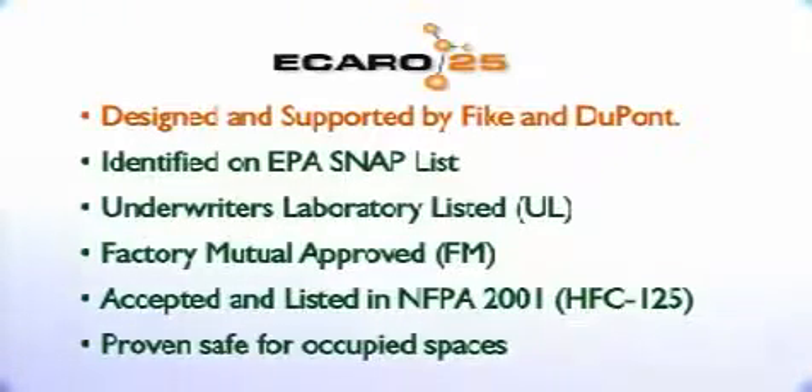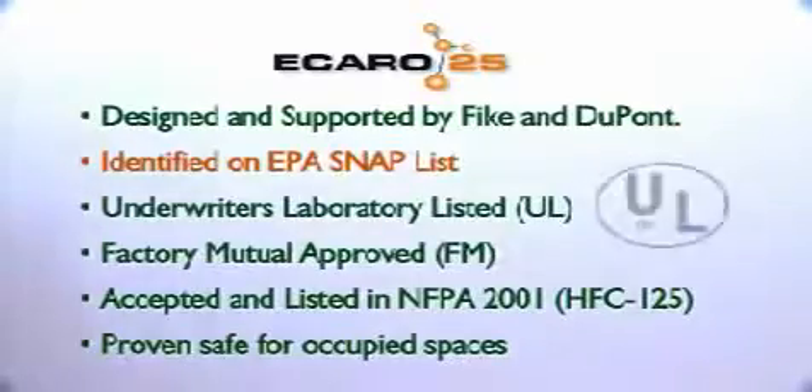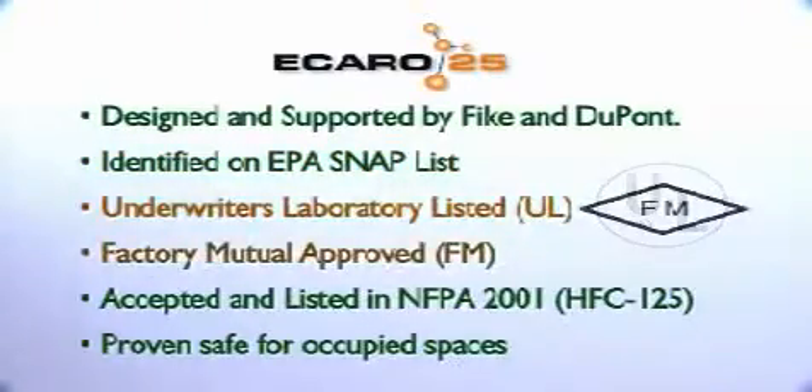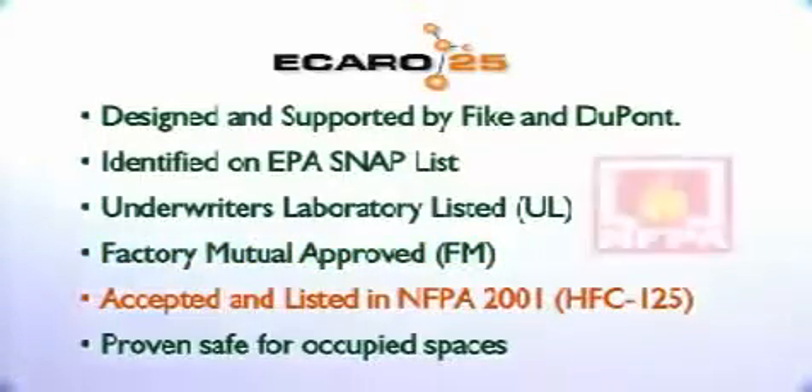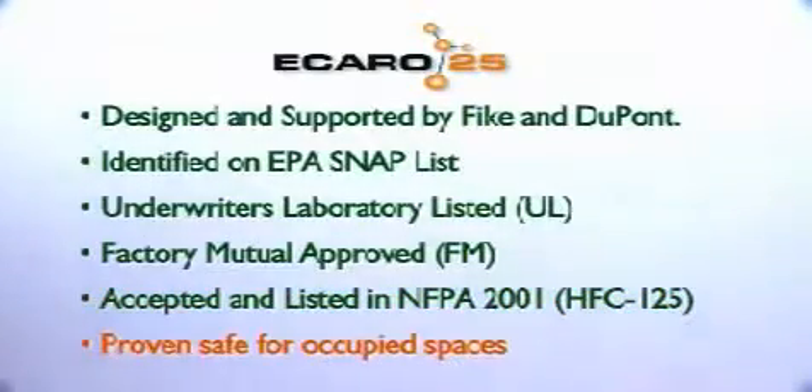Plus, ECARO-25 has been recognized, accepted, and approved by agencies in the fire protection industry. ECARO-25 is identified on the EPA SNAP list as an accepted Halon alternative. It carries the UL listing and FM approval of both the system and agent. It is accepted and listed in NFPA 2001. The design concentration is proven safe for occupied spaces via the EPA-sponsored and NFPA 2001-accepted PBPK modeling.